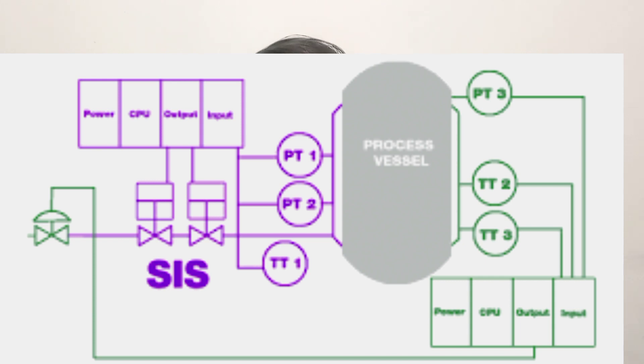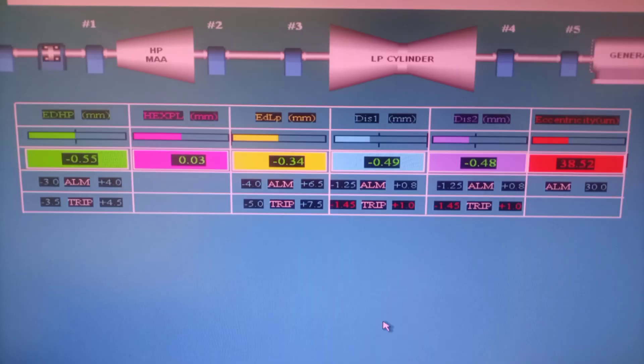As an example from the power plant I am currently working at, we have an emergency trip system which corresponds to the SIS system, and separate PLCs and process controllers are installed for this. In case of any abnormality such as over-speed protection, abnormalities in vibrations, differential expansion of the steam turbines, or temperatures of the bearings, it can simply give a trip signal to the DCS to initiate a trip of the system.